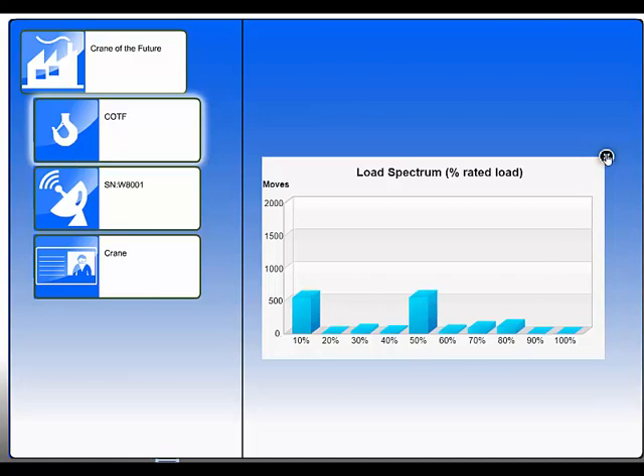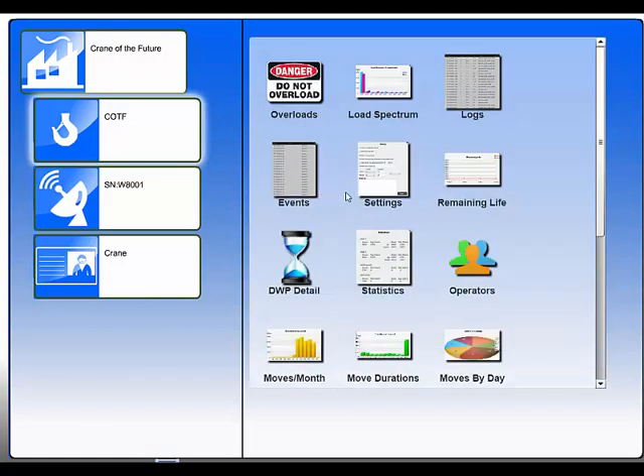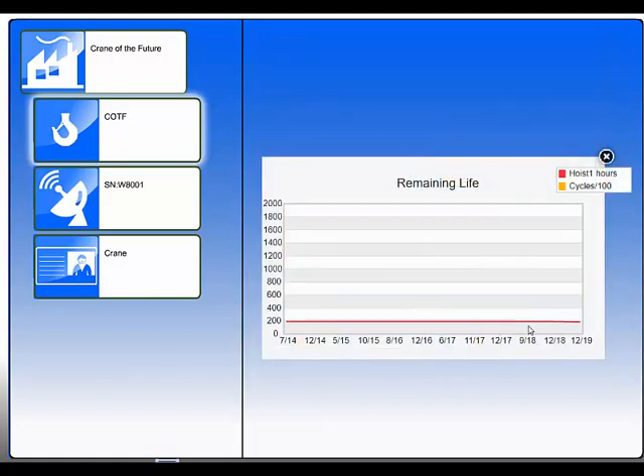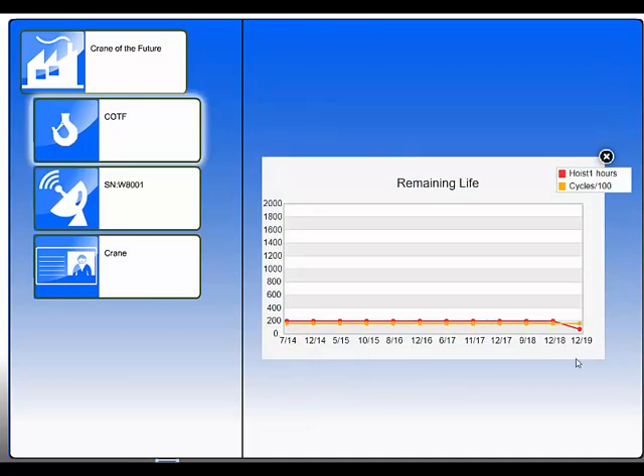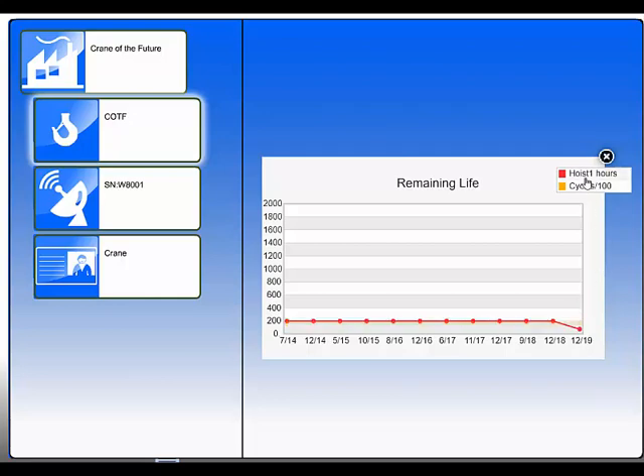We use that to calculate remaining life, and as you can imagine, we only do a little bit of work with that crane simulator, so I've accelerated the wear rate so we've got something to show you. You can see that this was a lightly used crane to start with, and we've consumed a fair bit of its life in the month that I've been doing these demonstrations with it. We monitor both the hoist hours and the structure cycles.